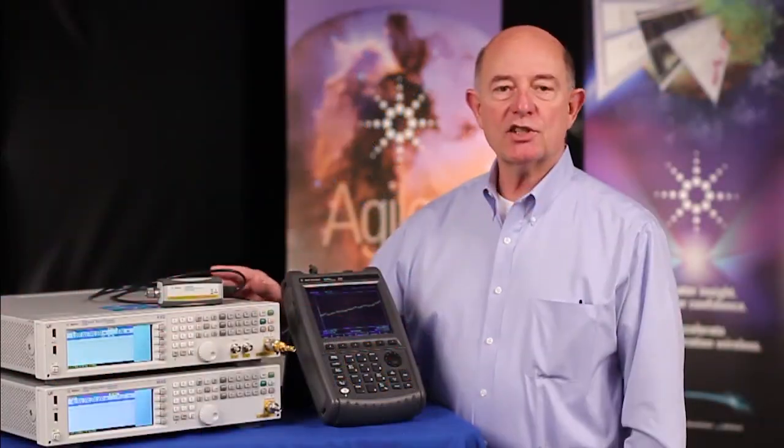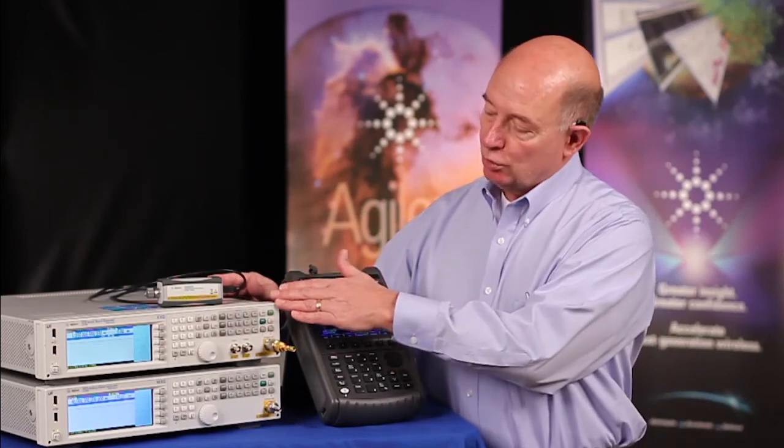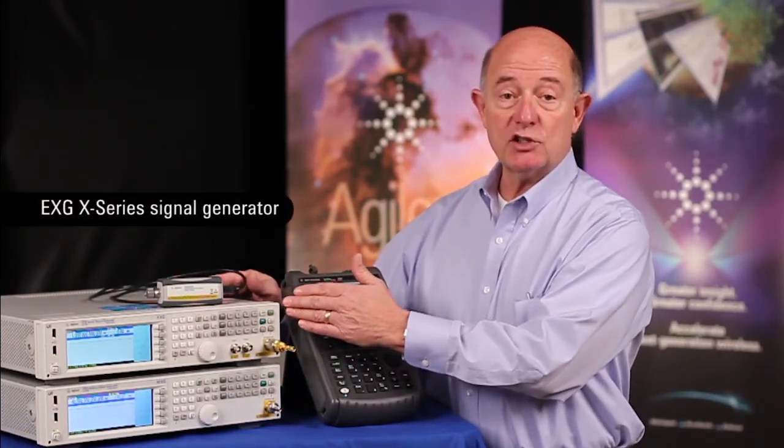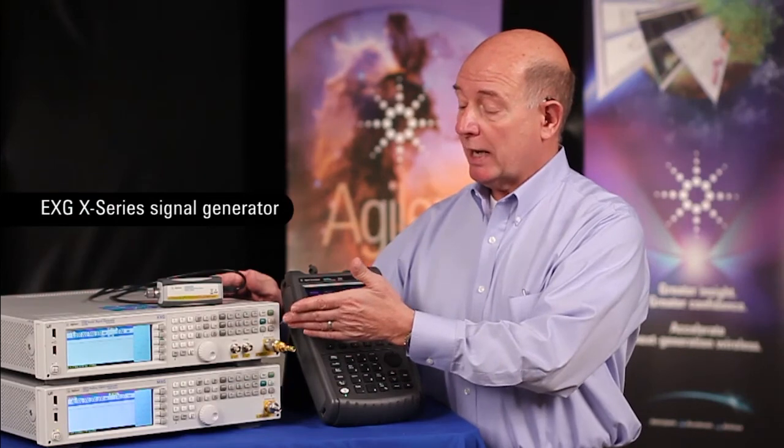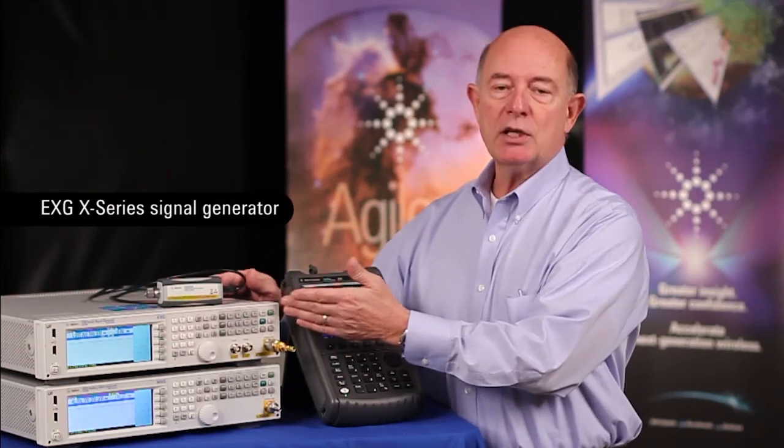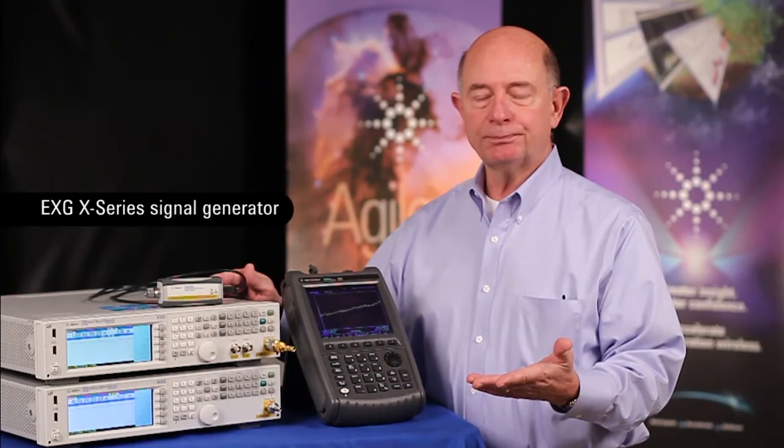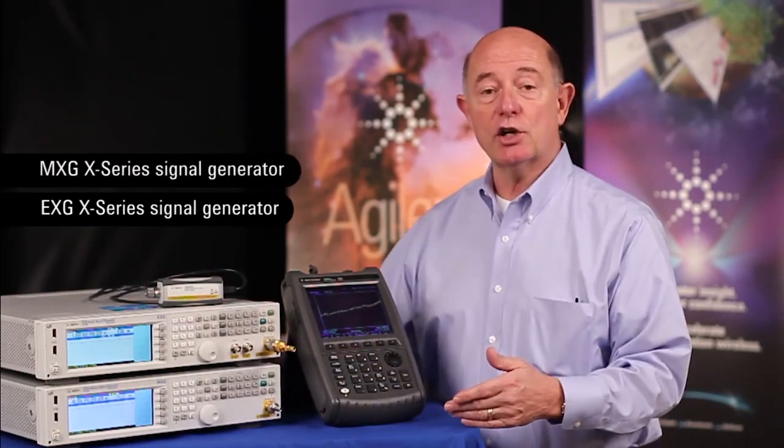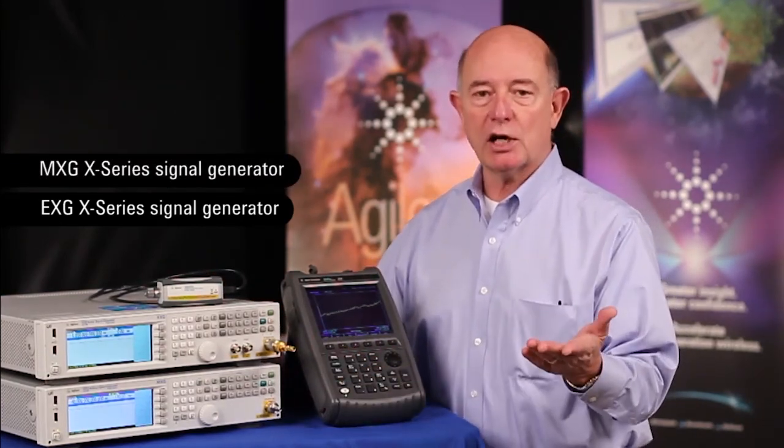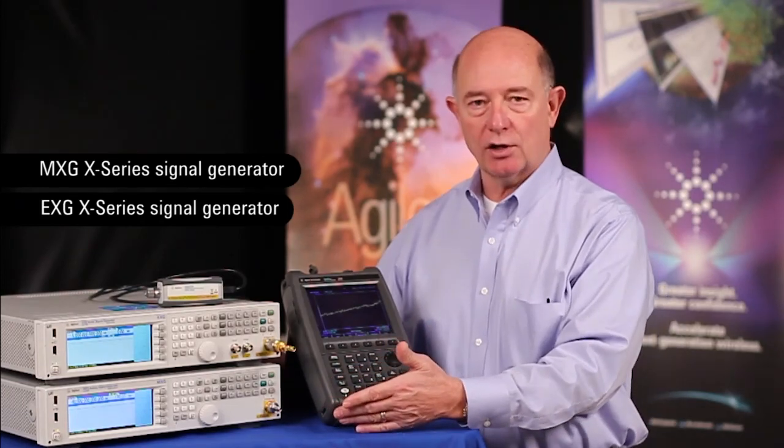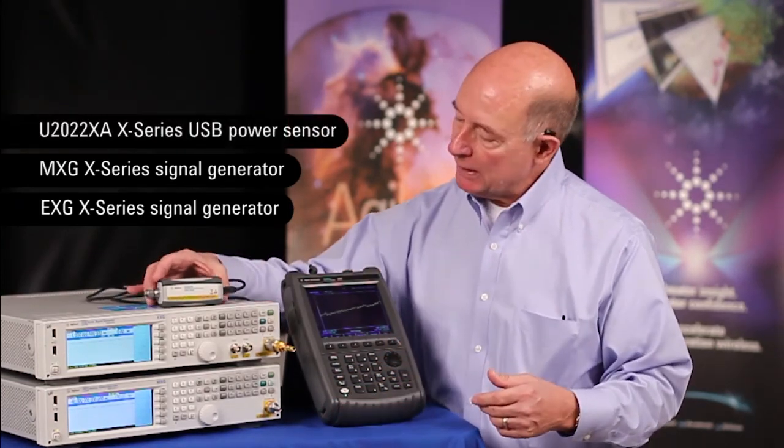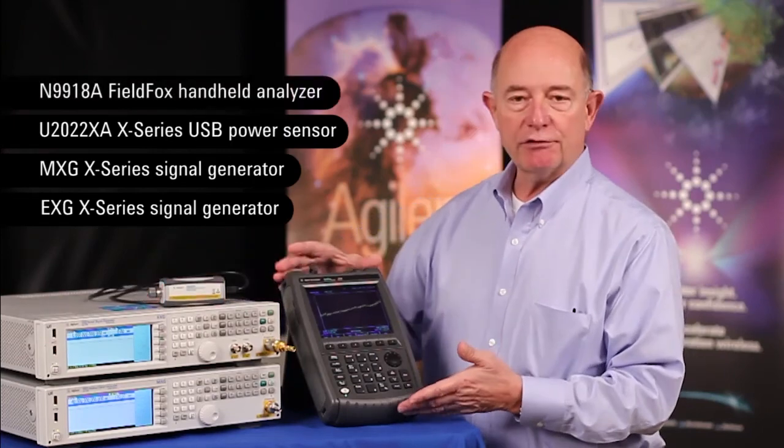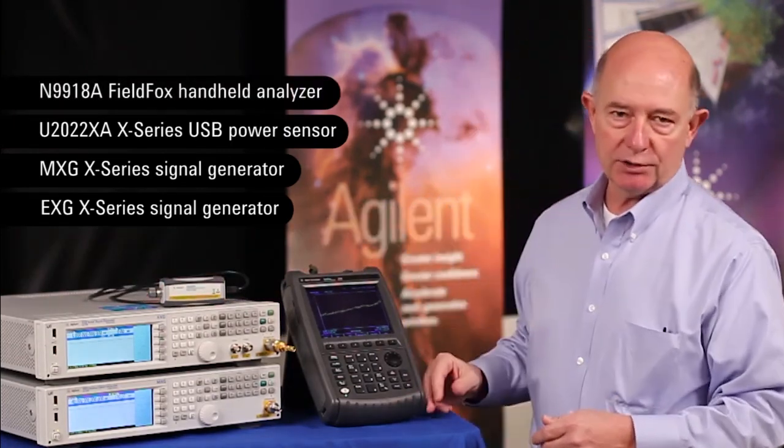Our test system today includes two signal generators. The first is a lower frequency signal generator used to generate the pulse stream from an air traffic control civilian radar. The second is a higher frequency signal generator used to generate pulses for a military system at 10 and 40 gigahertz. Also, we'll be using the peak power sensor and FieldFox. So, let's take a look at those signals.